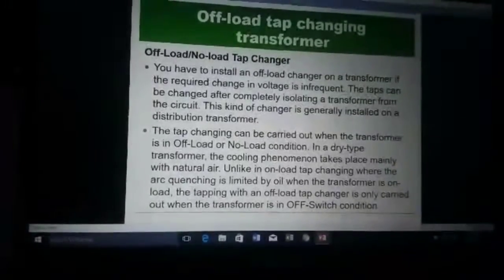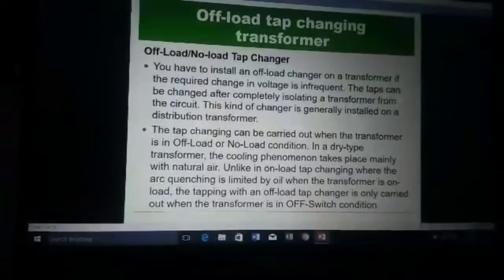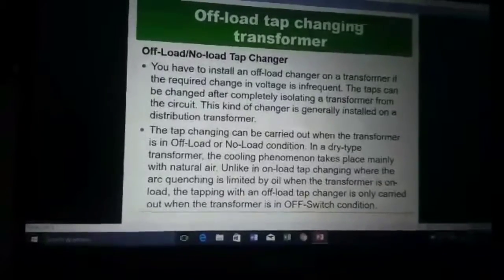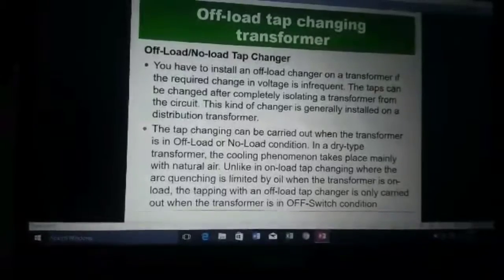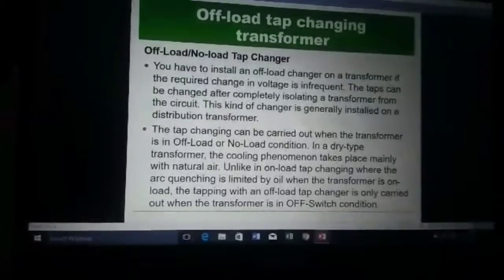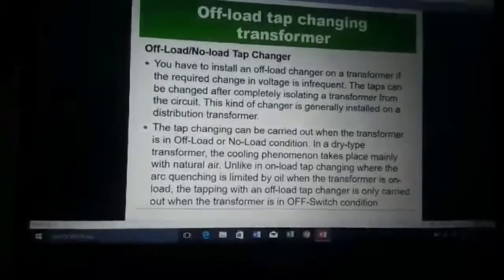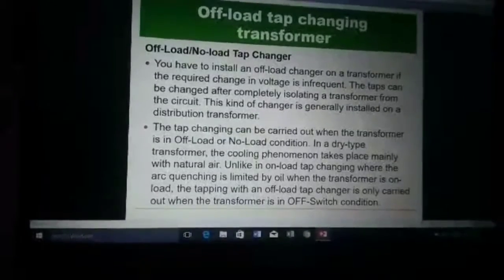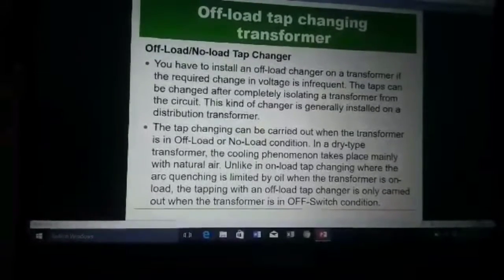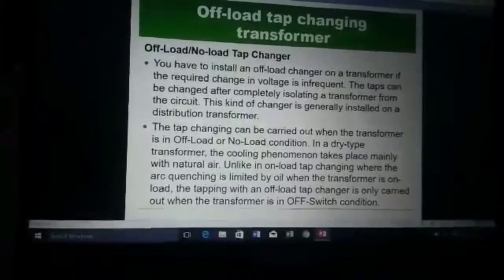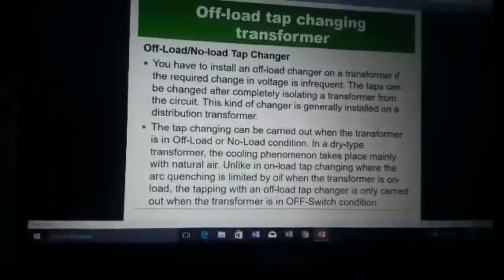In a dry type transformer, the cooling takes place mainly with natural air. Unlike in onload tap changing where the arc quenching is limited by oil when the transformer is onload, the tapping with an offload tap changer is only carried out when the transformer is in off-switch condition.